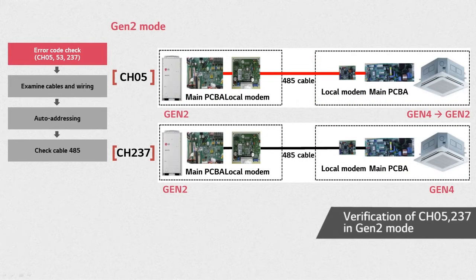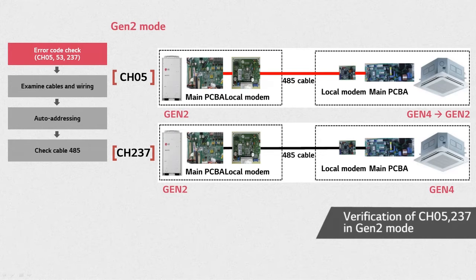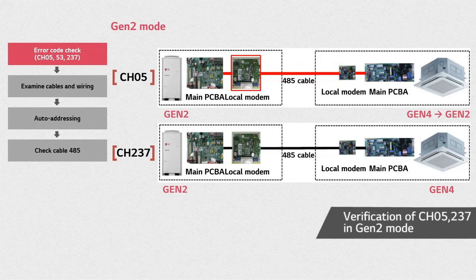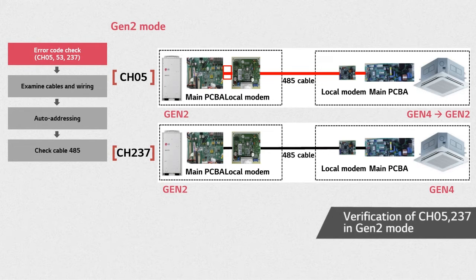When the IDU and ODU are set in Gen2 mode, CH05 indicates an error between the indoor unit main PCB and ODU main PCB. When error CH05 occurs, first, check the connection between the indoor unit local modem and the main PCB. Second, check the local modem state. Third, check the 485 cable between local modems. Fourth, check the outdoor unit's local modem. And finally, check the connection cable between the ODU's main PCB and local modem.